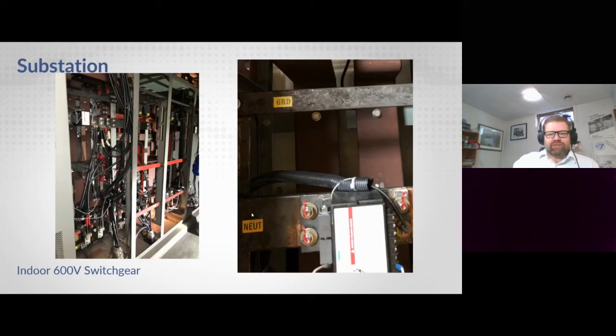This other one was very complicated because the original breakers didn't fit the bus bar, so we had to modify all the bus bars. Some of you will look at that ground bus and say massive corrosion, and you'd be correct. We had to lubricate and clean the bus bar connections for the breakers. We didn't clean all of them, we didn't have time, but we had to get back into that switchgear to measure.